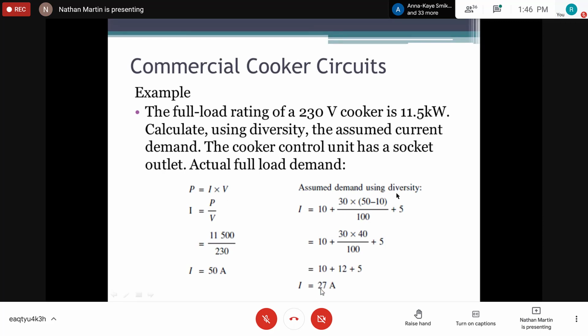And we are getting 27 amps, so we're talking about using a 4 mm cable, right? So in this case, we cannot use the 2.5 millimeter cable. We definitely have to use a 4 millimeter cable.